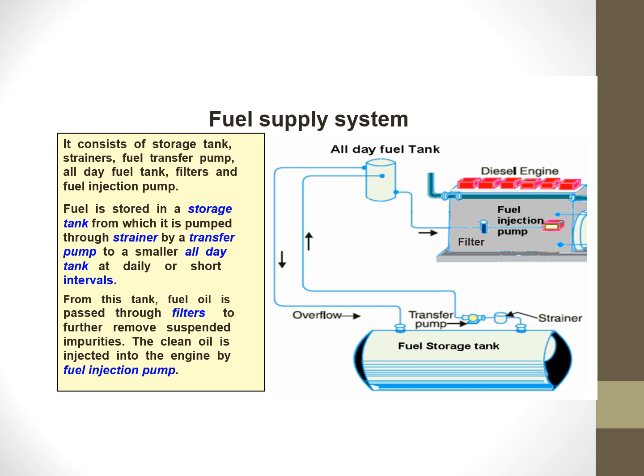Here we have the fuel supply system. The fuel will be supplied through the oil filter and strainer, by means of a pump, to the day tank. If the oil is overflowing, it will come back to the fuel storage tank.